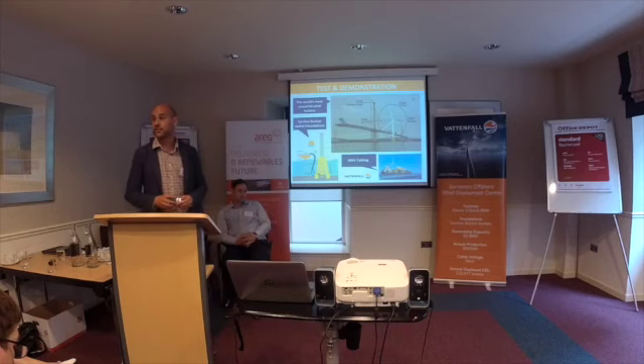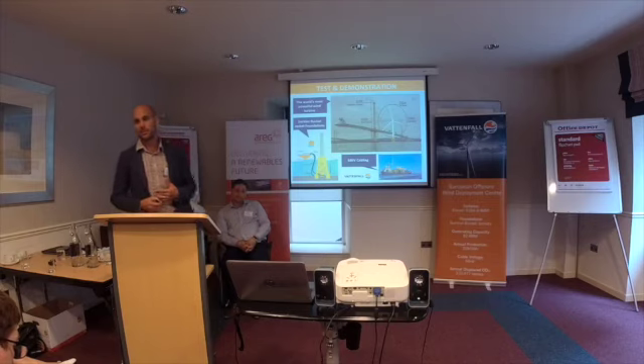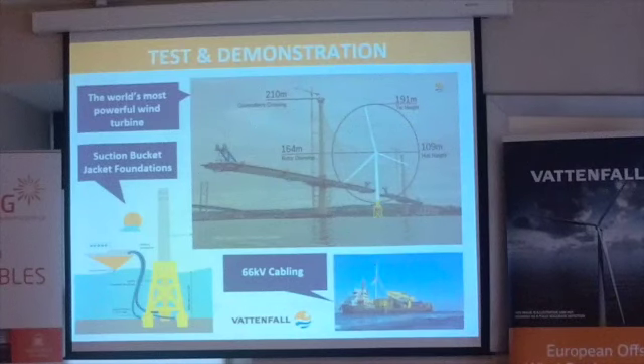Traditionally, inter-array cabling on offshore wind farms has been done at 33 kilovolts, and the industry's been talking for a long time, as long as I've been involved in it, about moving up from 33 to 66 kilovolts. Why do we want to do that? It's to reduce electrical losses in the system and to enable us to deploy less cable offshore.